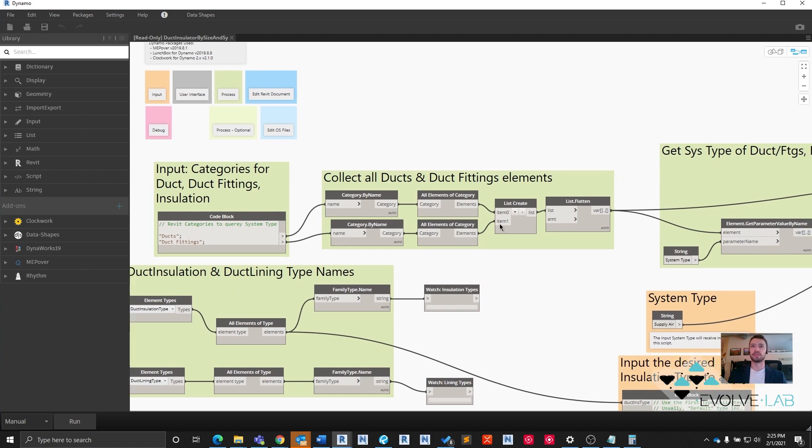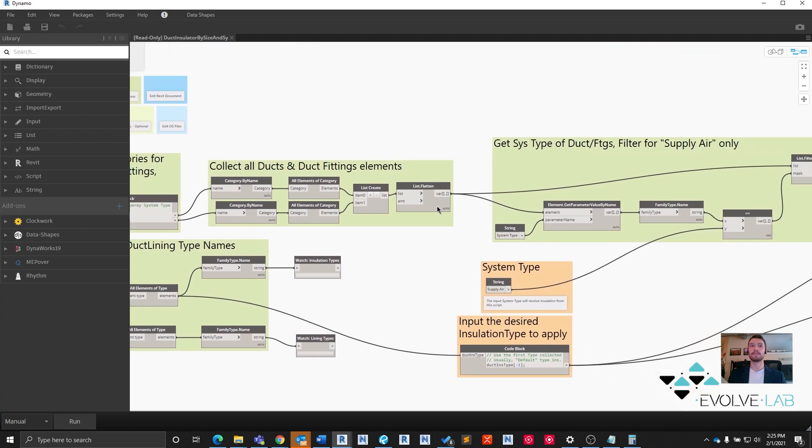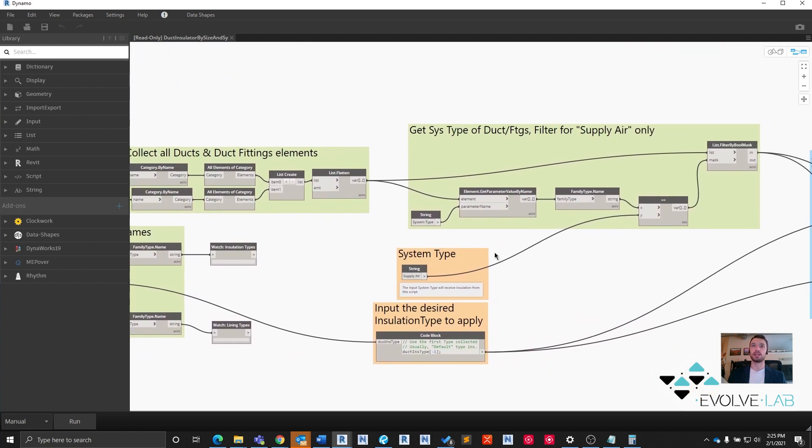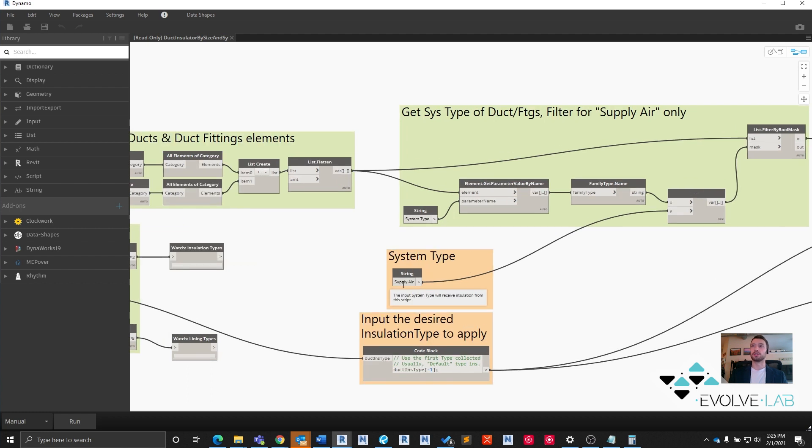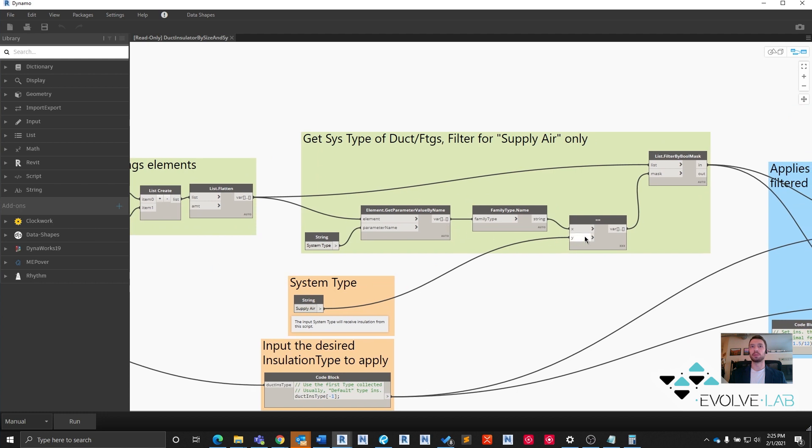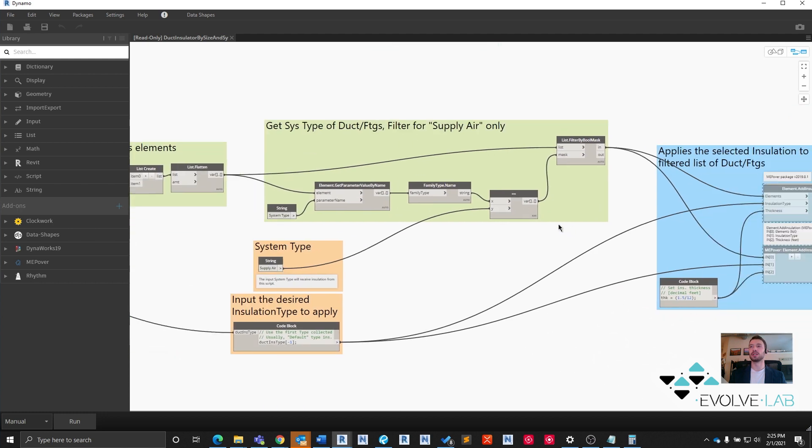We collect all of our duct fitting elements, put them in a list. Then we extract the system type we're looking for. For this duct system, duct supply air usually gets insulation, so we're going to look for supply air systems. By running a simple comparison, list filter by Boolean mask using that comparison. The filter results here: this is all of our ducts and duct fittings that are of the system type supply air that we specified.